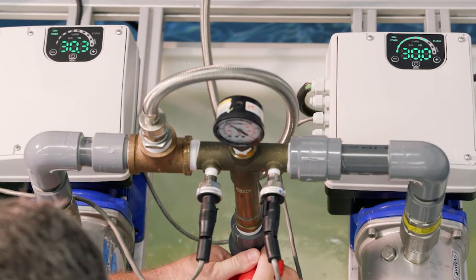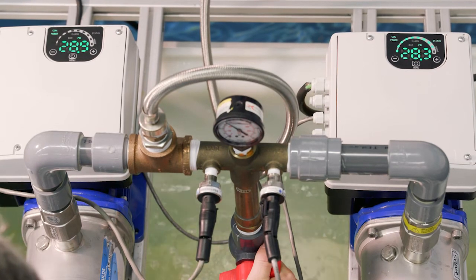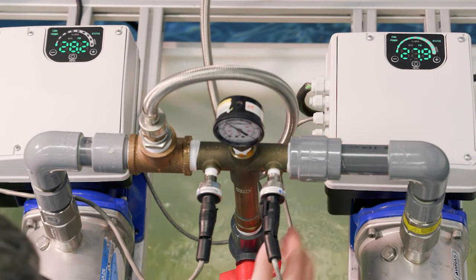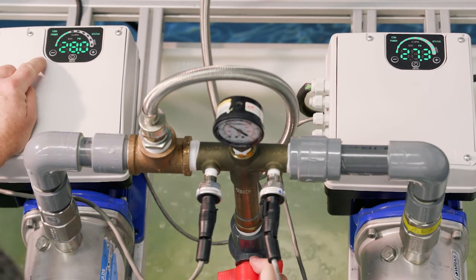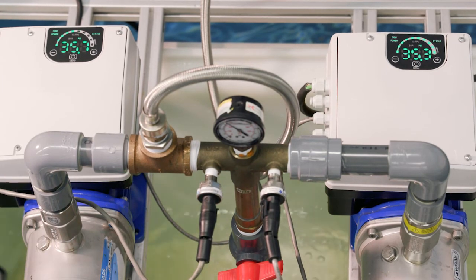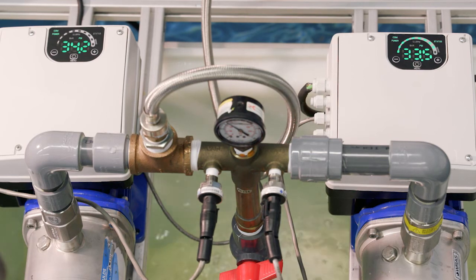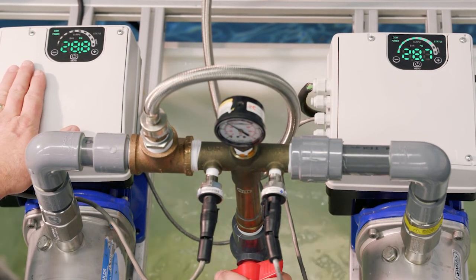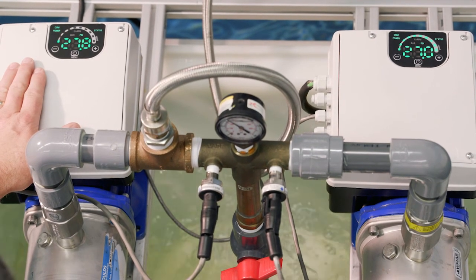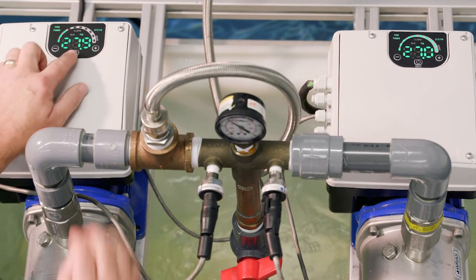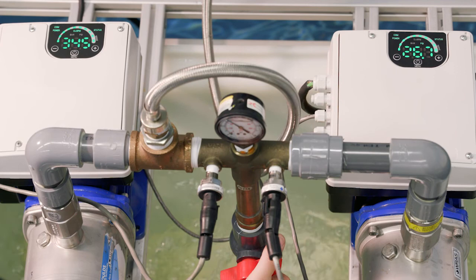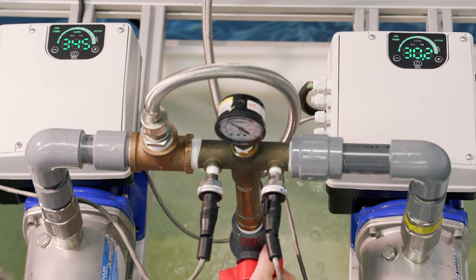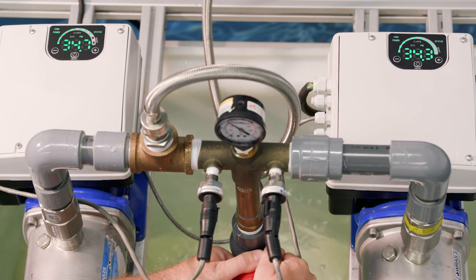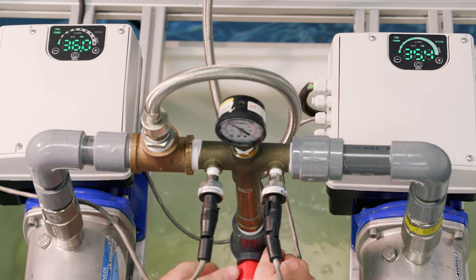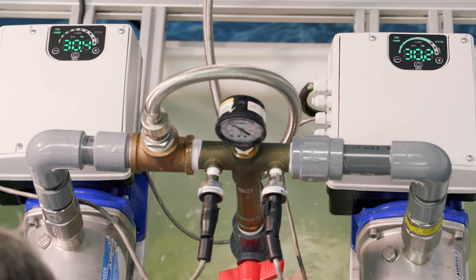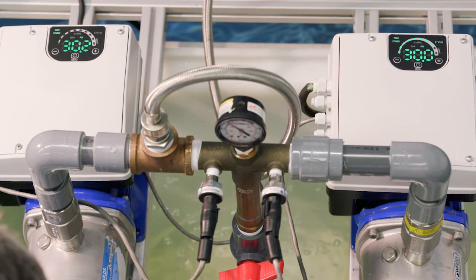All right, let's see if we can show you that again. So we got full speed. We can't keep up with the demand. It turns the lag on. And your lag is going to be the pump that varies. You see pump 2 on now. Let's look at speed. And your lag is always going to be the one that turns off before your lead. We'll slowly crank that down. We can see the lag is turning off, and now we only need 1 unit.